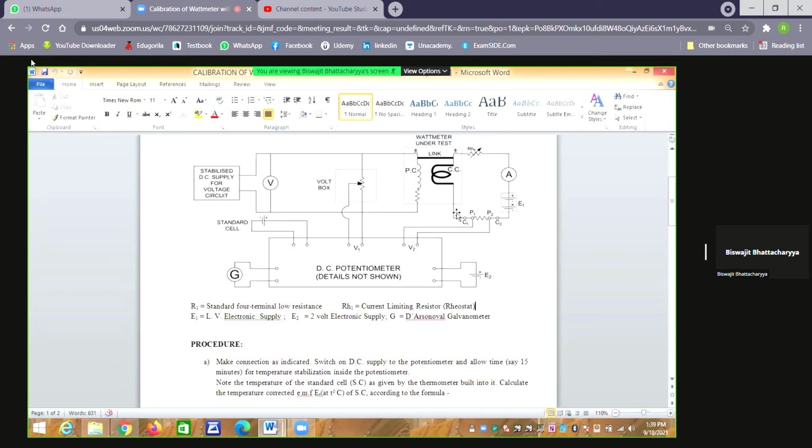So the other side of the current coil has a voltage of some millivolt, but the other side of the pressure coil has a voltage of a few hundred volt. So again, the other nodes of the two coils are widely different. Isn't it? So again, some electrostatic force or torque will come, a capacitive coupling will be there dynamically. So some error will come again.